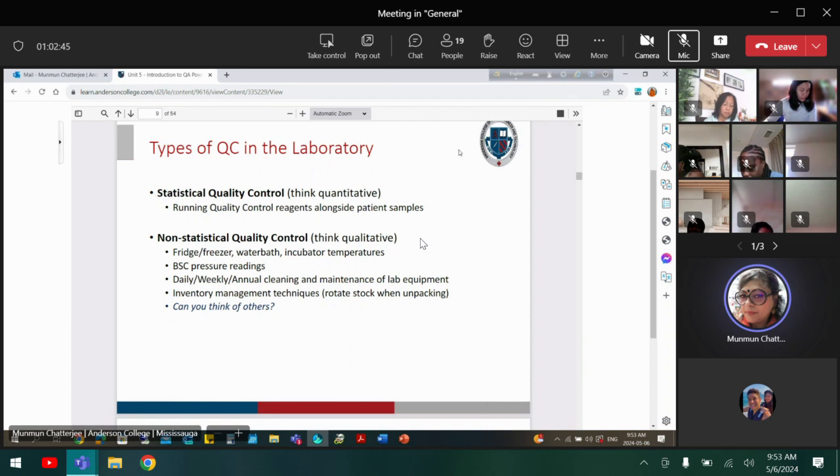First, you are going to change your solution and other things to make sure whether the instrument is working properly. So with the new batch, if it is giving the same value as the standard, that means the instrument is okay. But if your previous standard and your new standard are not giving the same thing, if there are deviations in the values from the standard value, that means there is a problem in the instrument. So that's why you rule out step by step what the problem is, to give the quality control.